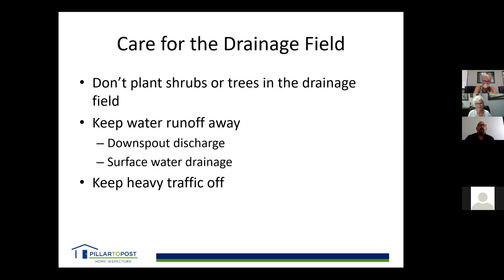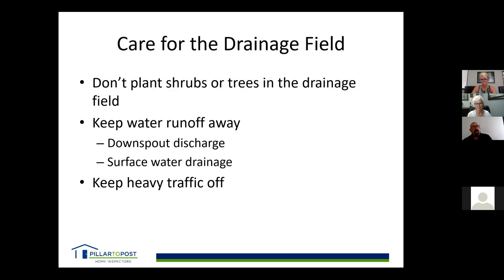To look after the drainage field: don't plant trees over it, because roots want water and will grow right into the pipes, requiring you to replace the drainage field. Don't allow low spots — extra water pooling and draining down saturates the soil so it can no longer drain. Keep heavy traffic off the drainage field — don't drive trucks or cars over it. It can cause compaction and damage the tiles, which are only 12 to 16 inches underground.